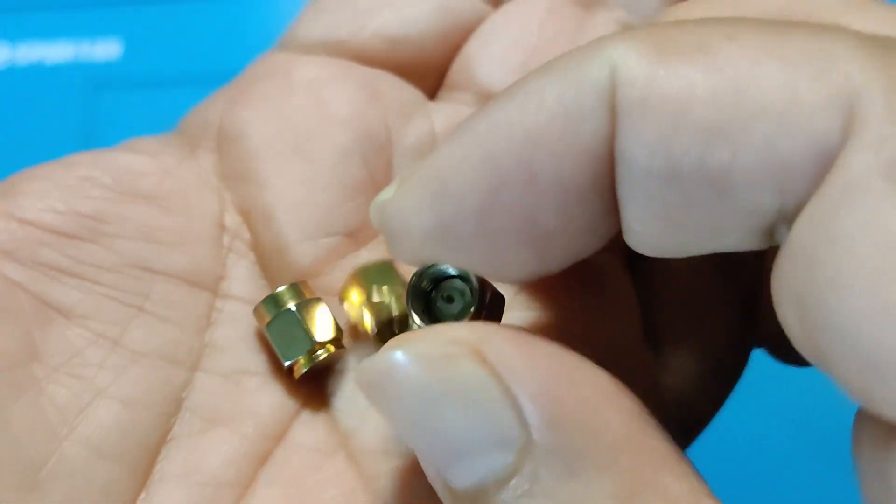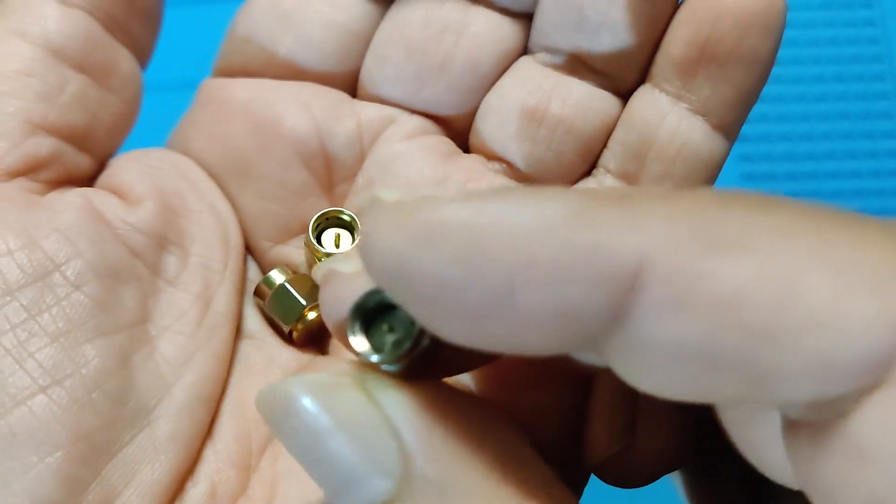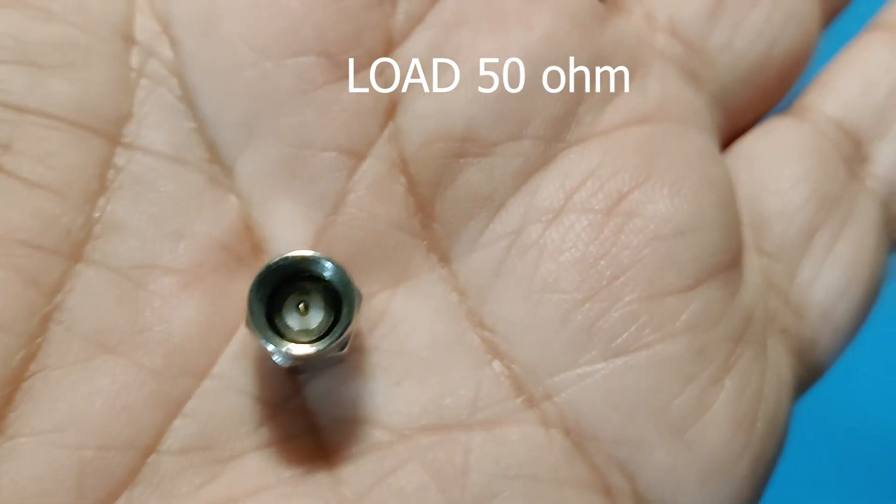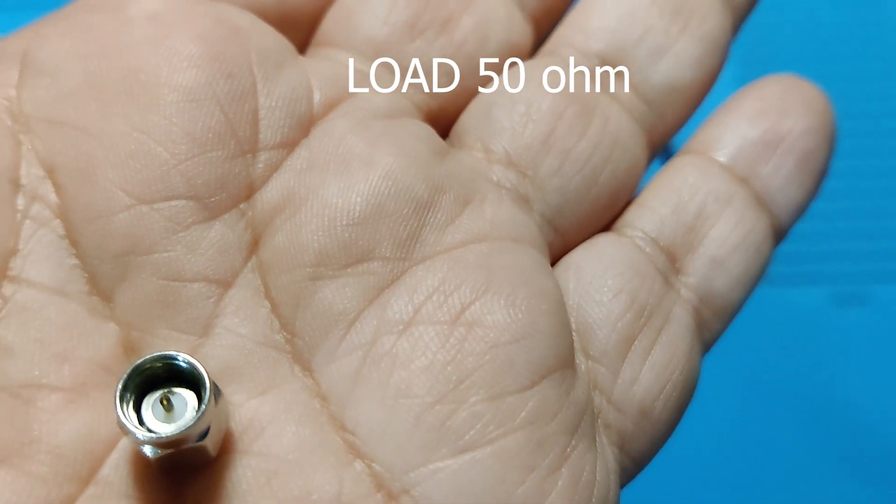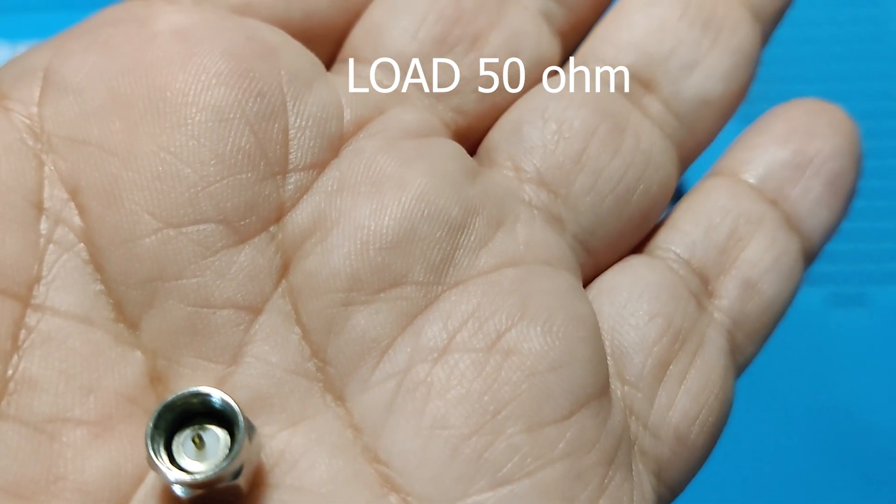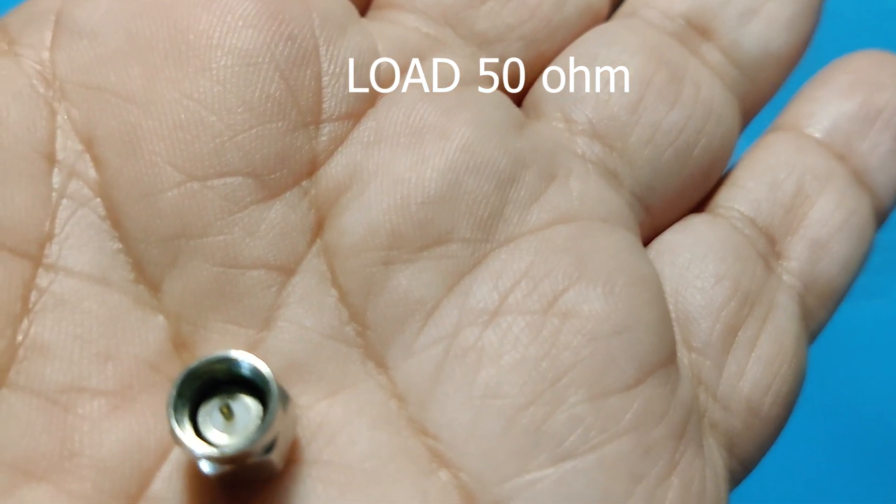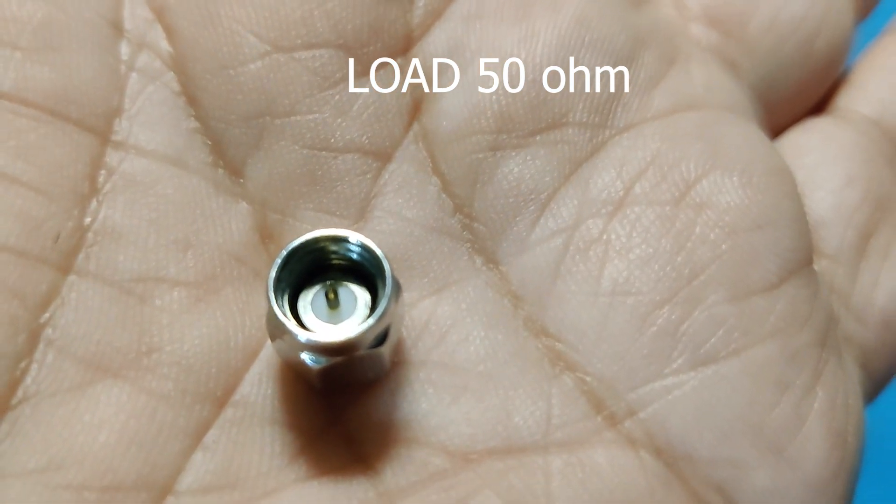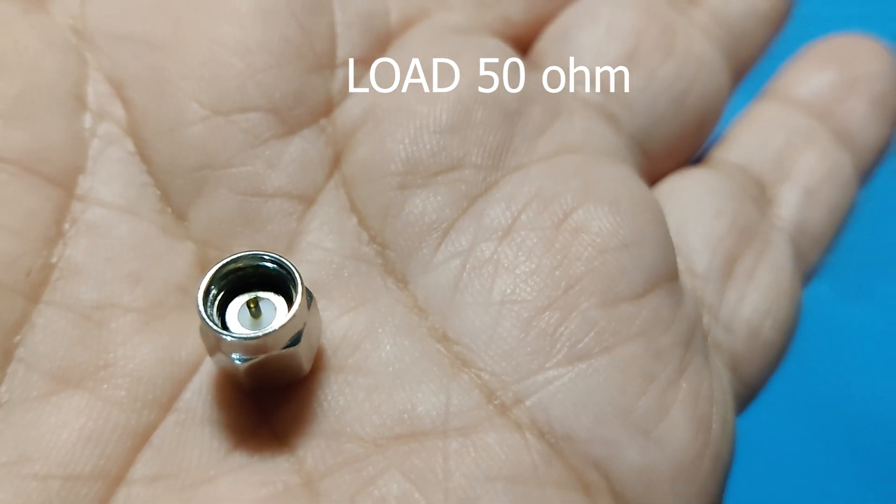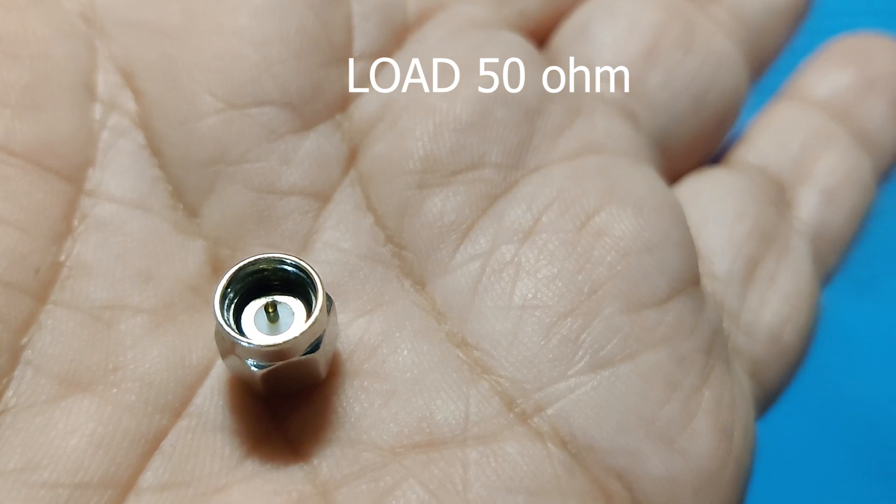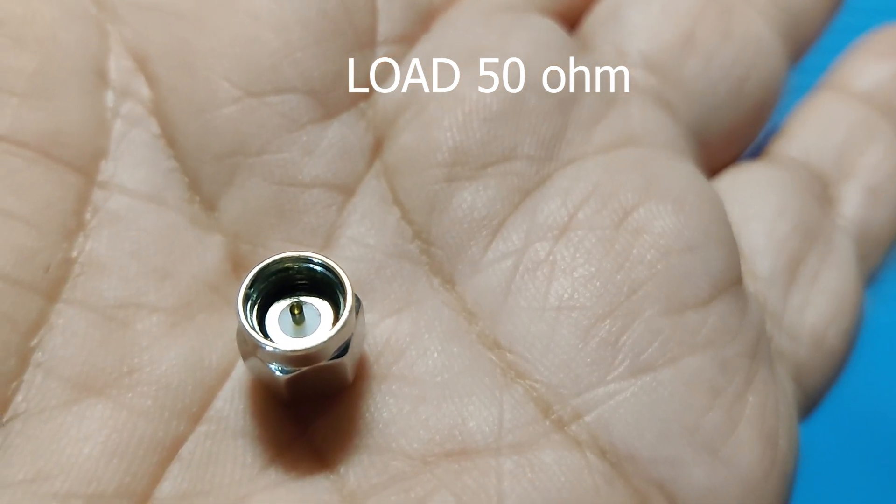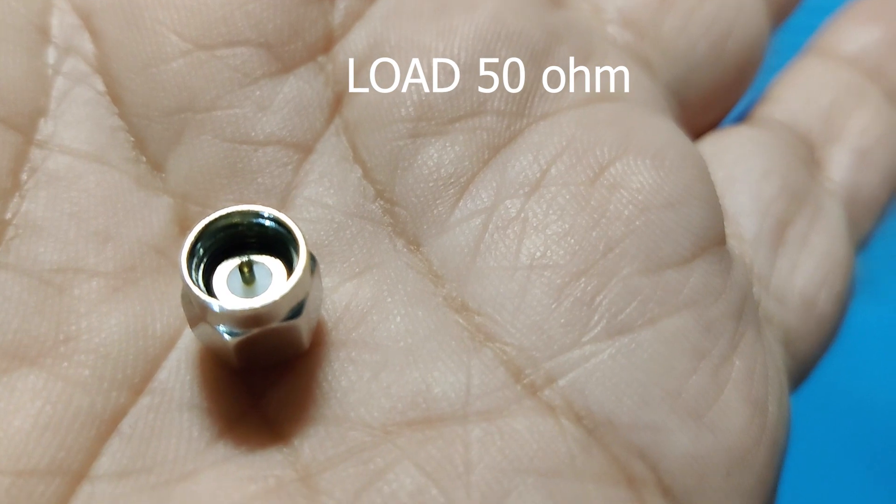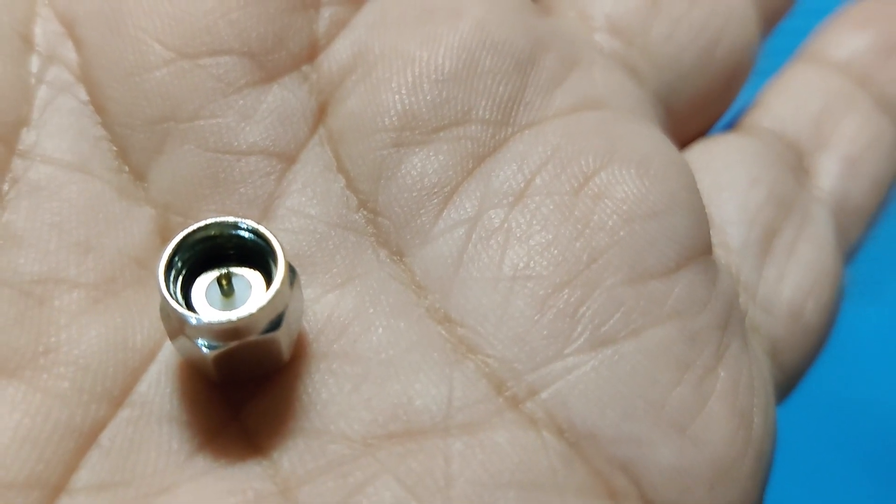If you look closely at the load, you will see a center pin which is isolated from the outer body of the load with a plastic-like material. If you check it with an ohmmeter by placing one probe on the body and the other on the center conductor, you will see a 50-ohm resistance.